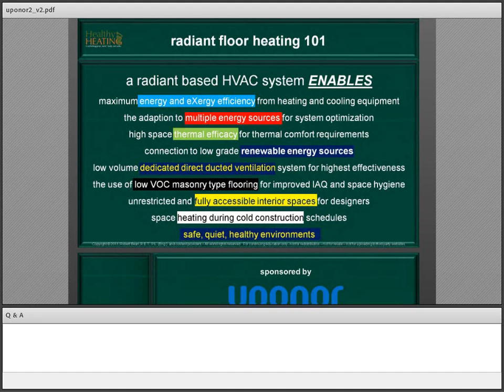And then, of course, it enables us to use dedicated ventilation systems. There's no confusion about what the air is supposed to be doing. Air is very good at taking out particulates, what I call the decontamination process. Air is very, very good at dehumidification or humidification. So it's an excellent medium for addressing the respiratory needs of the occupants. But air-based systems don't perform the same way in terms of thermal comfort. So assigning thermal comfort to a radiant-based heating system, and ventilation strictly to the respiratory needs, makes it a really nice combination for a hybrid.